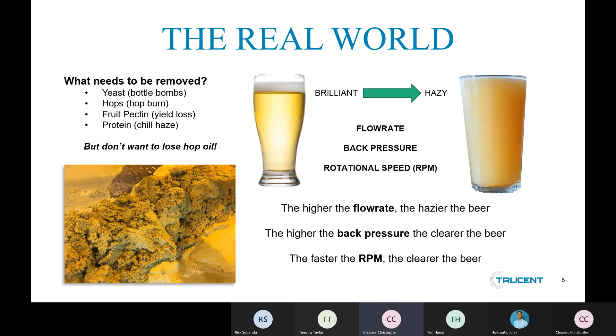Now, it is important to remember that each of these variables has a safe working range depending on the make and the model of centrifuge that you're running. So it's important to have good training from the manufacturer to understand what those safe limits are, especially with rotational speed. It is very dangerous to overspeed a bowl, and there are certain speeds at which critical harmonics happen that could cause damage. So you want to know where that safe working range is for each of these variables.